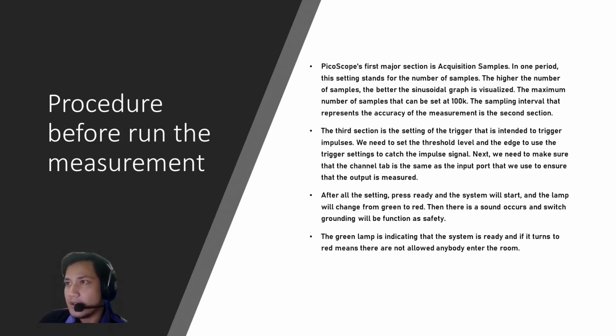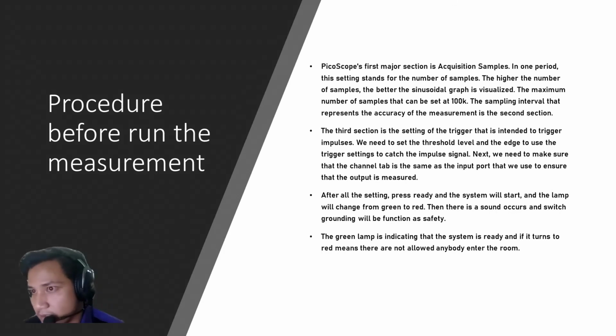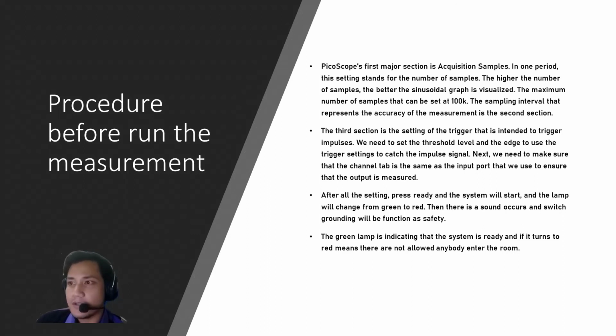The first major section is acquisition sample in one period. This setting stands for the number of samples. The higher the number of samples, the better the sinusoidal graph is visualized. The maximum number of samples that can be set is 100K. The sampling interval, which represents the accuracy of the measurement, is the second section. The third section is the setting of the trigger that is intended to trigger the impulse. We need to set the threshold level and the edge to use the trigger setting to catch the impulse signal.